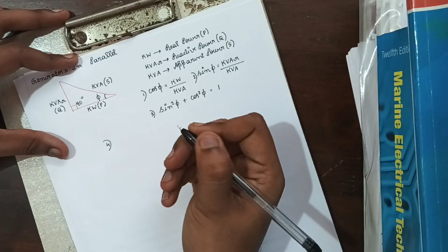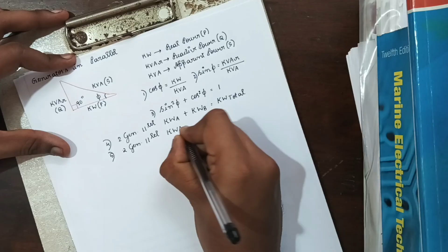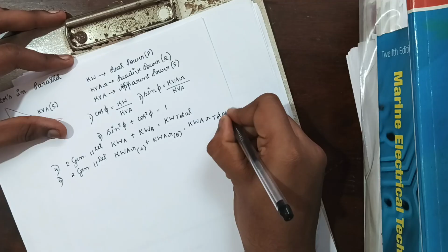Now, the fourth formula is that if two generators are running in parallel, then the real power kilowatt of generator A plus the real power of generator B is equal to the total power, that is kilowatt total. Next, the fifth one: if two generators are running in parallel, the kVAR of generator A plus kVAR of generator B is equal to the total reactive power, that is kVAR total. So these formulas we have to remember.